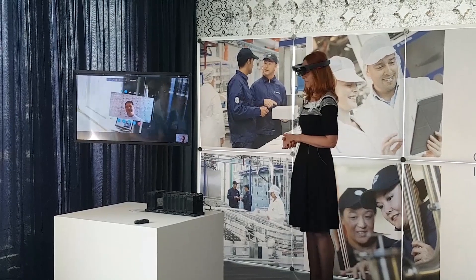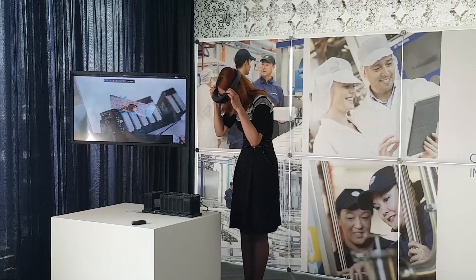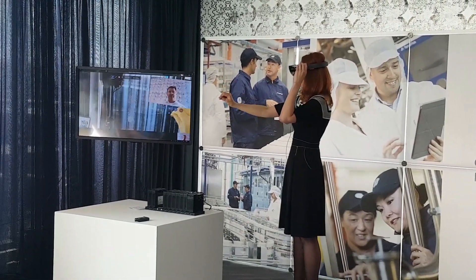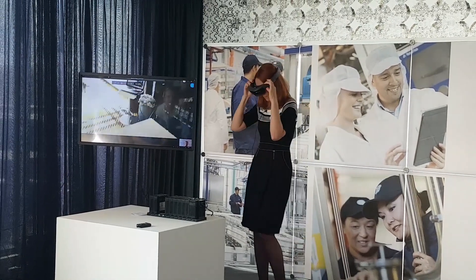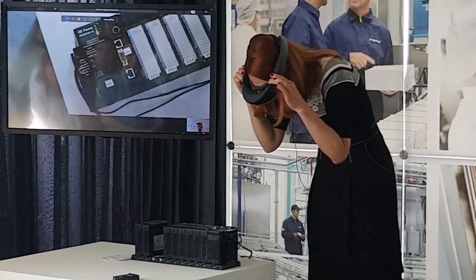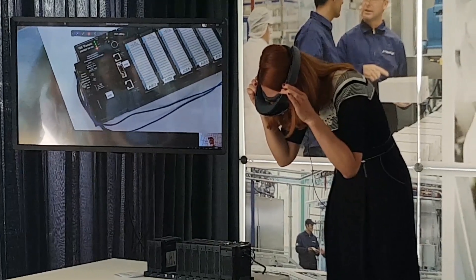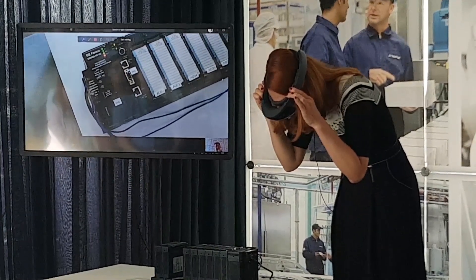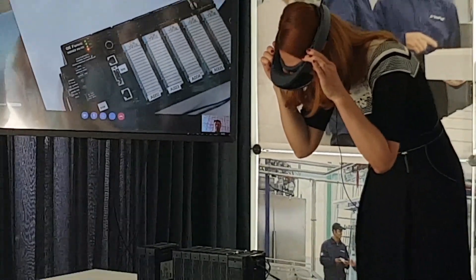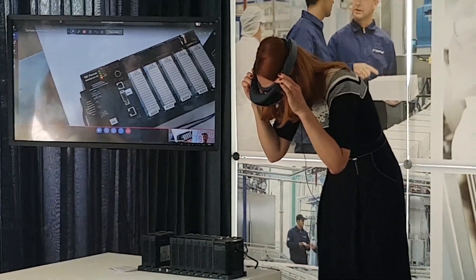Of course, please show me the problem. Can you put the screen a little bit there for a while? Exactly — let me take notice. Pin it there. What I see here is a GE Fanuc Series 90-30. It's written 'run mode' in green. And I think your question is relating to this red indicator? Yes, red — just to make it clear, let me make it visible so we can see.